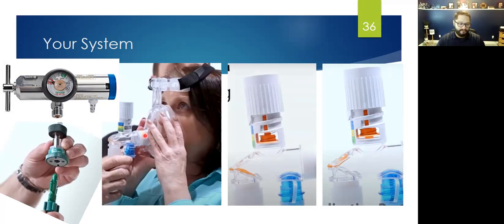And what's interesting about your unit versus most other units on the market is, and I'll go into that probably a slide or two from here, more in depth, that why they're uncomfortable is because they're afraid they can overbreathe what that device can do. So you put them on a non-rebreather mask, and you're talking 15 liters a minute or so, and somebody can overbreathe that. They can breathe faster and more volume than that if they're really working to breathe. So I'm sure you guys have seen it. I know I have. Put a non-rebreather on someone, and in a few minutes they're ripping it off. Well, they're ripping it off because they're overbreathing the device and they're not getting what they need. And this device, because it delivers 140 liters a minute, test question, it's not likely that someone can or even possibly overbreathe that. So let them become comfortable, strap it to her head.